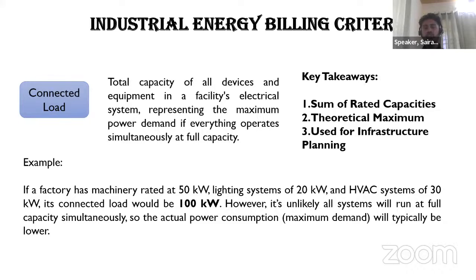It is also used for infrastructure planning. If you have 1000 kVA of connected load, then you will plan the entire infrastructure, like the bus bar and the transformers, accordingly. Also, you will go for the contract demand with the grid according to that. First you have to plan which equipment will be in load condition at which time. Then you have to consider the planning of maximum demand.